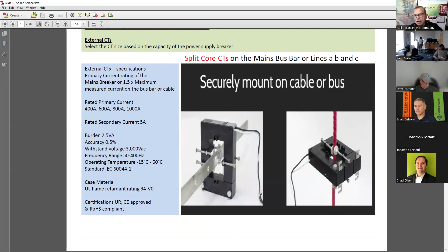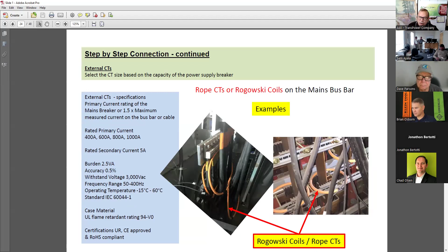But we noticed that there are a lot of problems happening because of that. So we went to Rogowski coils, which is a rope CT, which is a snap-on CT, a lot easier to install across a group of cables on line A, line B, and line C, or the bus bars. So you can use Rogowski coils or rope CTs. How many of everybody on this call may have already seen this, right? So it's not new to you.